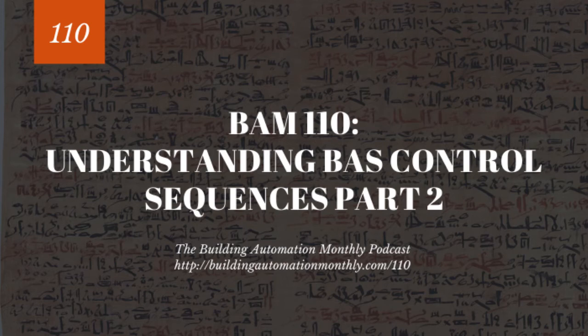Here's a trick. And I promise we'll get right back to the sequence. I did not plan on having so many segues in my show notes here. But here's a really cool trick I like to do. When the unit is unoccupied and there is no airflow from the air handler supplying it, I will disable the PID loop and I will command the damper to 100%.